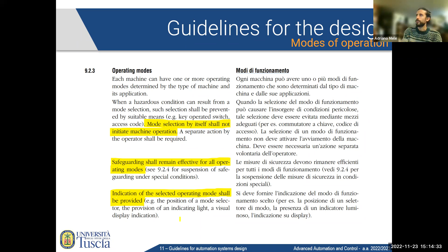So once we have fulfilled all these steps, we have taken care of the safety of operators around the machine, the safety of property, safeguards such as interlocks, two hand controls, continuous action controls, and all these kinds of things. We have our emergency stops, our mode selectors, we have documented how we intend to program our plant, produced wiring diagrams, mechanical part drawings, checked the interfaces, done functional tests, all these things. Then, after all that, we can actually design the main control logic.